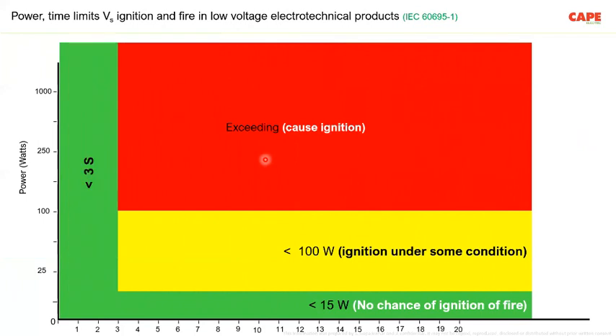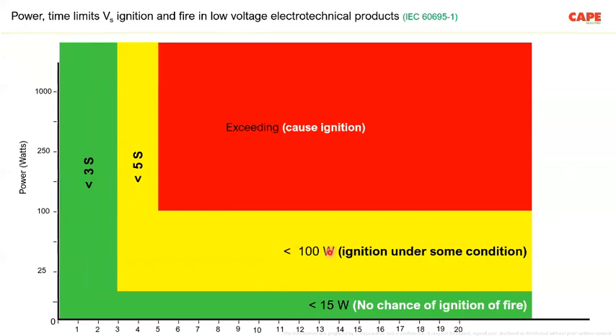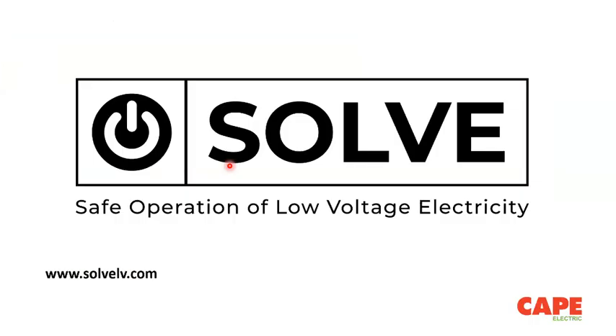Also, I told you last time, the energy classification: any connected equipment of lesser than or equal to 15 watts during a fault or an overcurrent is not supposed to ignite fire. And 100 watts, of course, it may create under some condition. More than 100 watts is a little bit dangerous. But if you are able to disconnect the supply within 3 seconds, of course, you achieve safety from fire. Less than 5 seconds or maximum 5 seconds and limited to less than 100 watts, probably it is still safer. But exceeding the limits of 5 seconds and 100 watts is always risky. This means that if we analyze fire accidents, and if it is really from the short circuit, these are some of the techniques which can be used for analyzing the circuit.